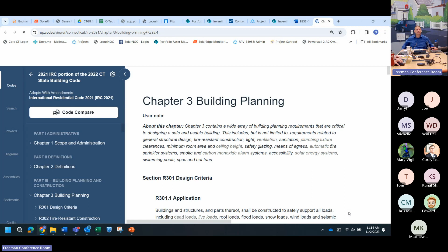As I understand it, all the batteries in our program do have the UL 9540, but these are the IRC codes and do apply for those kinds of batteries as well. When you're talking about battery cabinets, that's the enclosure that comes with a battery. Correct, this is an additional enclosure on top of that, the walls in an indoor setting. And the battery enclosure is the metal case that the batteries are designed to be installed in. Always use the metal case the batteries are designed to be installed in.